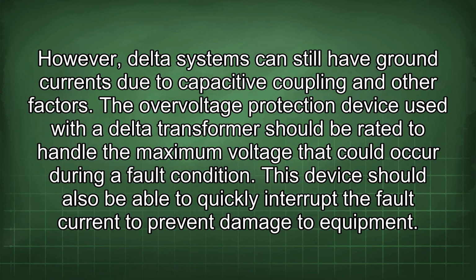The overvoltage protection device used with a delta transformer should be rated to handle the maximum voltage that could occur during a fault condition. This device should also be able to quickly interrupt the fault current to prevent damage to equipment.